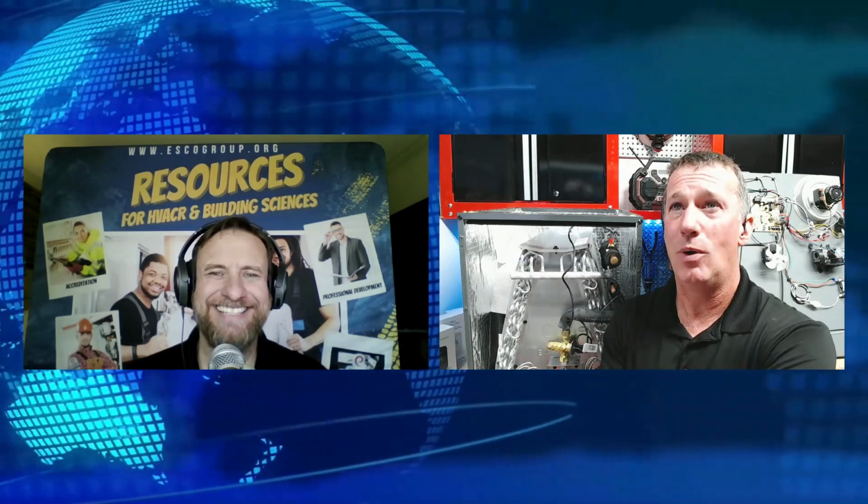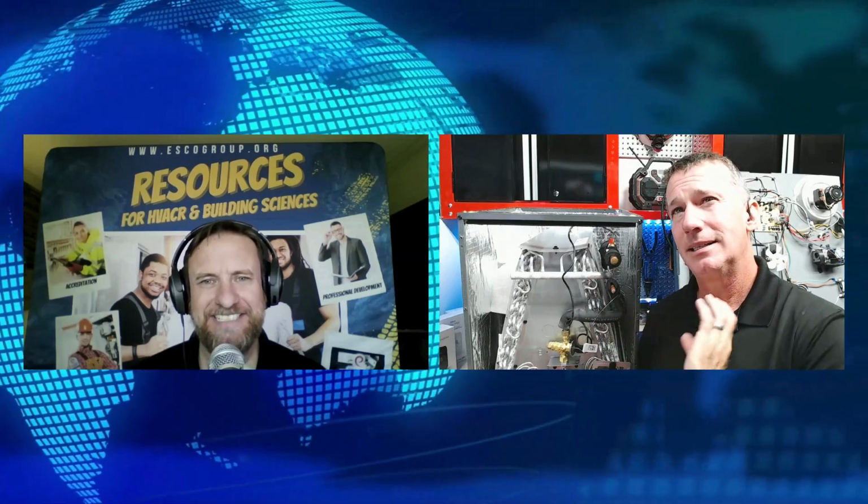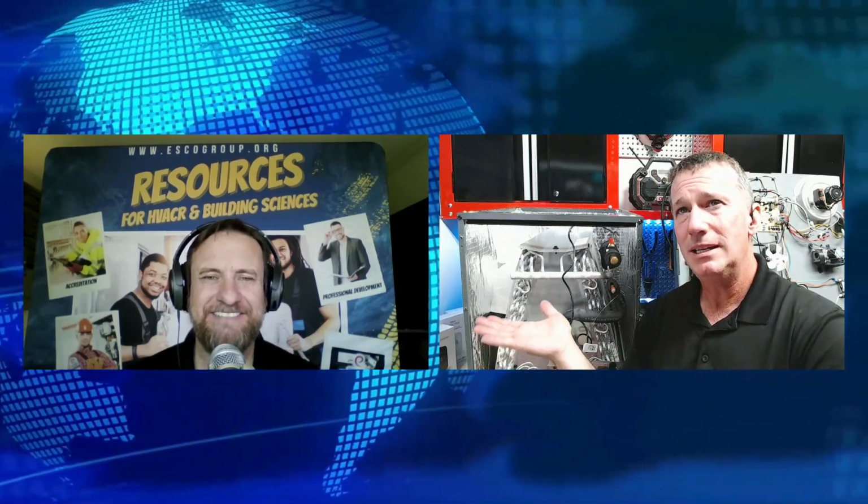We're actually going to run this thing through a mitigation to see what actually happens, to verify our theory about what should happen if we were going to put this thing into mitigation. So in the scenario, we would have a refrigerant leak at the indoor coil, and it's a large enough leak that it can meet the lower flammability limit for that refrigerant. And then we should go into a state of mitigation.